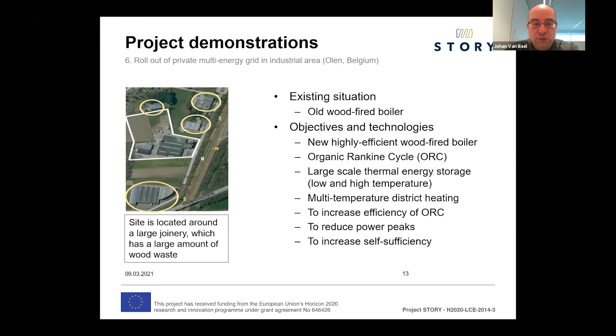Before the project, they had an old wood-fired boiler where they burned the waste wood from their manufacturing processes. The aim of this project was to install a new wood-fired boiler, including an organic Rankine cycle, to produce electricity locally for use in the SME zone, and to increase flexibility by adding thermal energy storage tanks to control the ORC more flexibly and reduce peaks in heat demand.